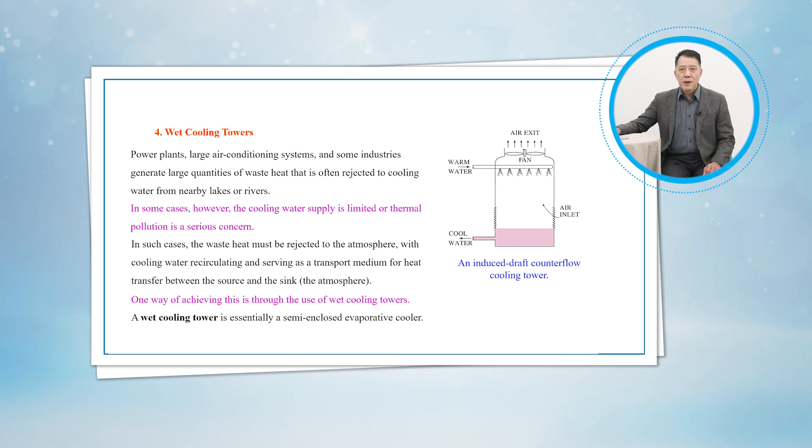The cooled water collects at the bottom of the tower and is pumped back to the condenser to absorb additional waste heat. Make-up water must be added to the cycle to replace the water lost by evaporation and air draft. To minimize water carried away by the air, drift eliminators are installed in the wet cooling towers above the spray section.